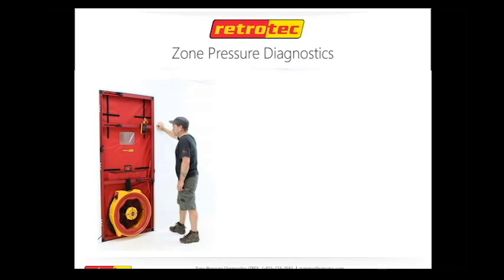So hopefully we're able to enlighten you that these are not overwhelming tests to do. And if you're doing a pressure pan, you already understand the concept: when you have a pressure pan over a duct, with the blower door running and numbers above 2, closer to 5, you have significant leakage from the outside moving into the ducts and into your register, and it shows up on your pressure pan. That's the same kind of concept you're dealing with here. Now I'm just going to use the gauge in a probe or gauge in a tube, and I can go around the house and try to find the focus for air leakage.